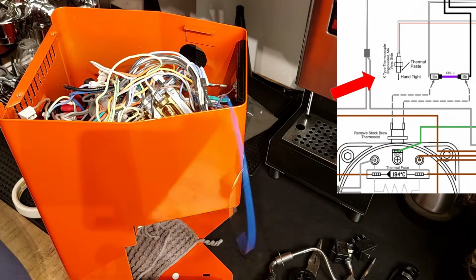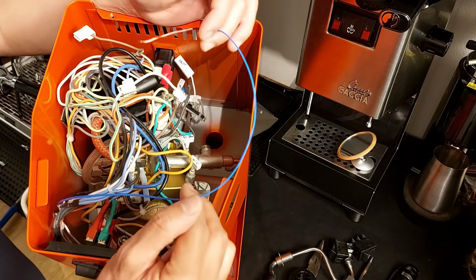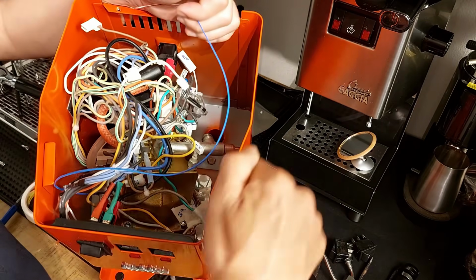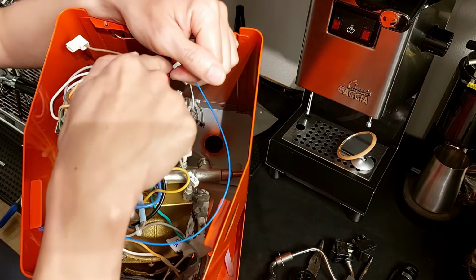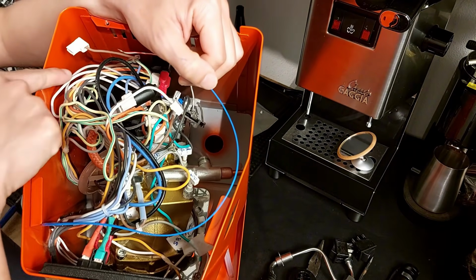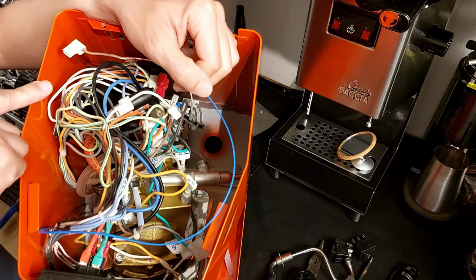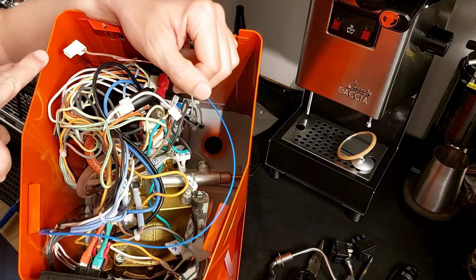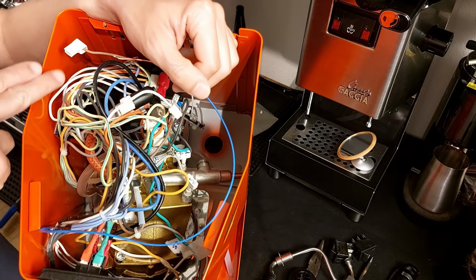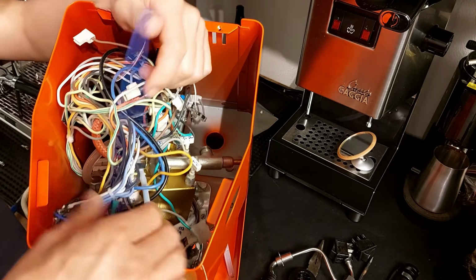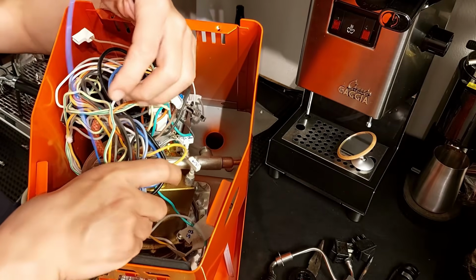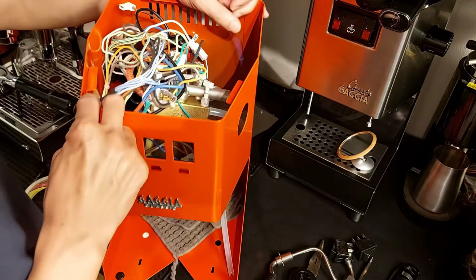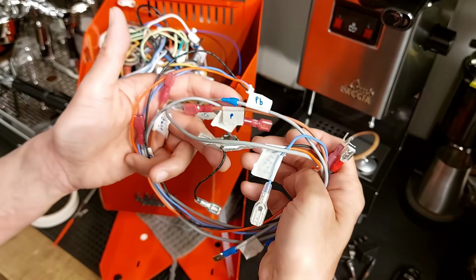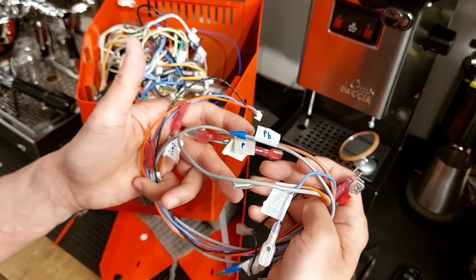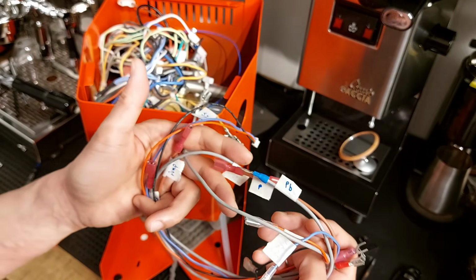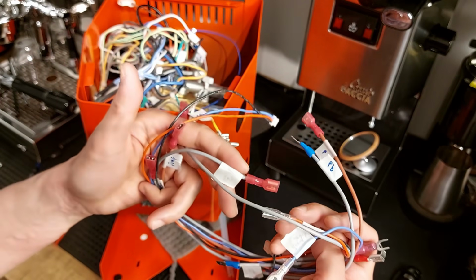Now we need to route this cable for the thermocouple around the front of the machine, not the back, which would be close to the pump area and subject to interference from the high voltage wires and electromagnetic interference from the pump and the solenoid valve. Let me route this cable now since it's easier, and organize it later. All the cables I received from Peak were previously identified following the schematics, making installation easier, more organized, and less subject to failures.